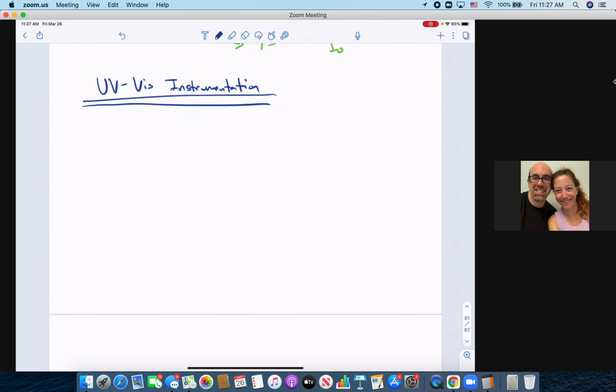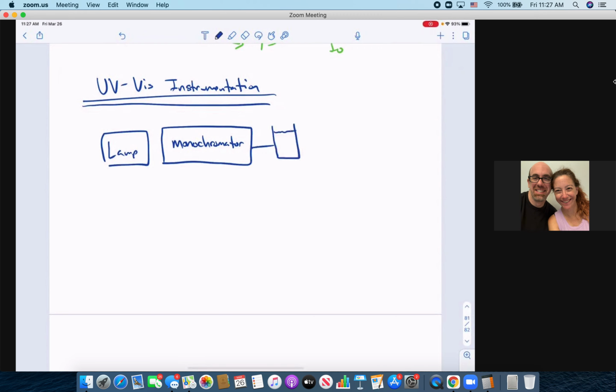All right. So in the case of UV-Vis, you need a lamp, some kind of light source. It could be an LED or a broadband lamp. Then you need a monochromator to select a particular wavelength. And the reason for that, again, is that we need that monochromaticity. We need to have a band of light that is narrower than our sample, so to speak. Then you need the sample itself, which is always going to be some kind of cuvette these days. And then a photodiode. We use photodiodes because when there's no analyte present, the signal is large, right? And as the analyte increases, the signal goes down. But the blank itself has a lot of photons going to the detector, right?